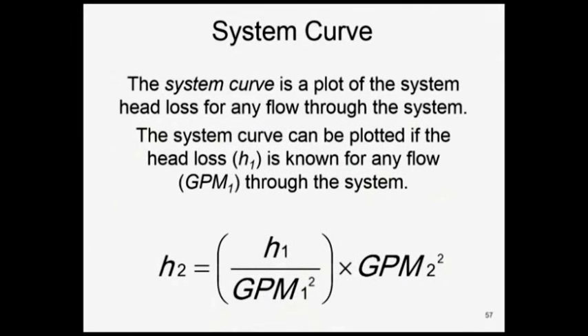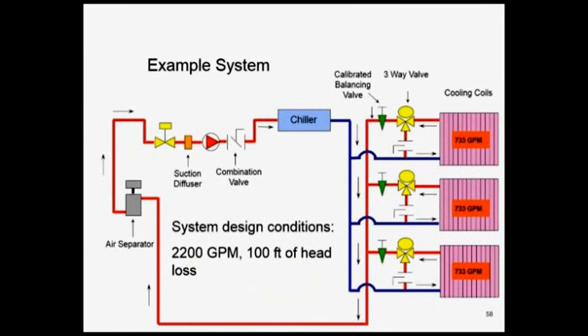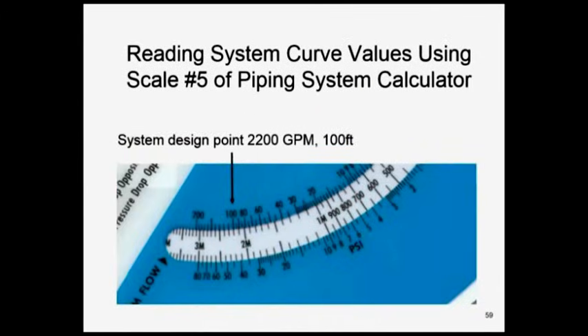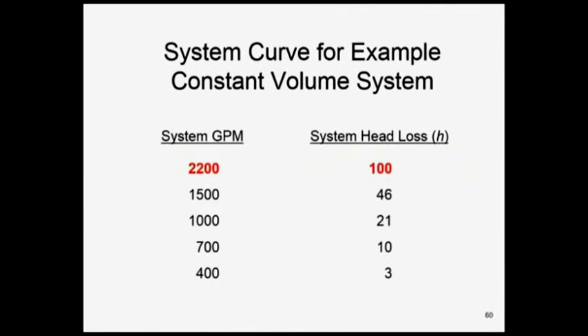We're going to keep the same little numbers. We're going to go back to our example of 2,200 GPM at 100 feet of head. We're going to go to our system curve scale 5. It can be the hard copy, any one you've got, and you see I've got it marked here at 2,200 GPM at 100 feet of head. I'm going to fix it. I know that point. And once I know that point for my system, I can give you the flow rate and head at any other set of conditions. I just leave it fixed. I read them all off, and this is what I just did. And you see how it follows that half, fourth. You see how the square functions work. So now I have the system curve for your system where you did the calculations and you told me it was 2,200 GPM at 100 feet of head.